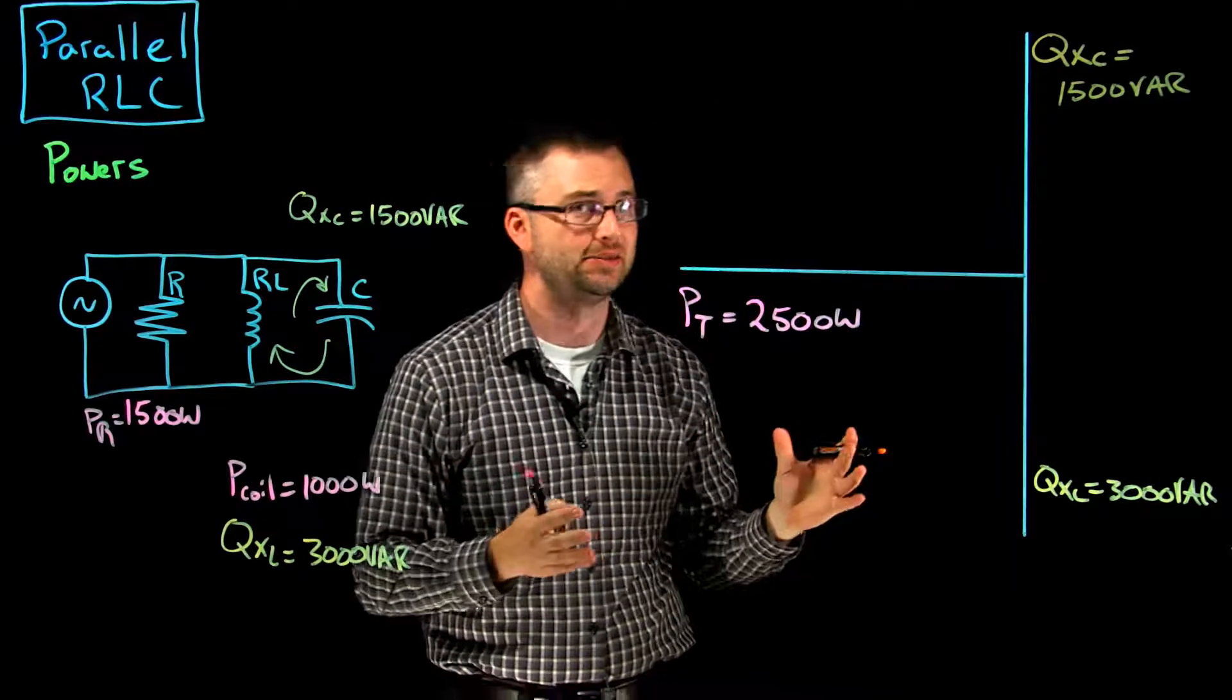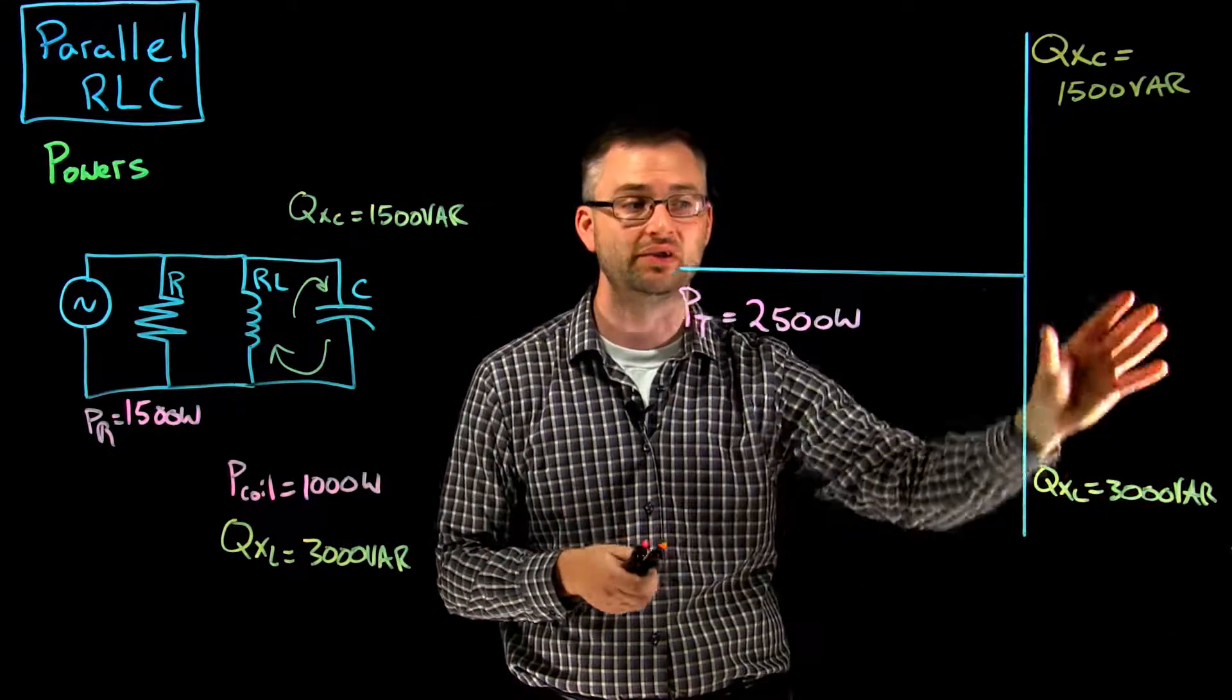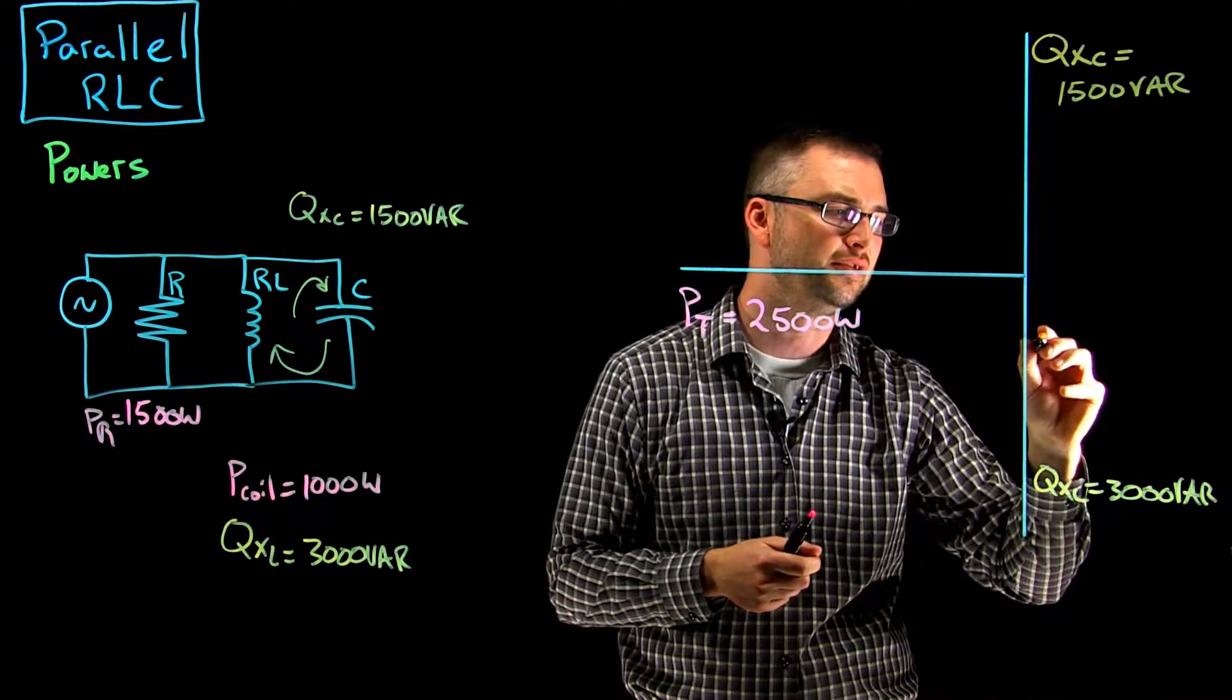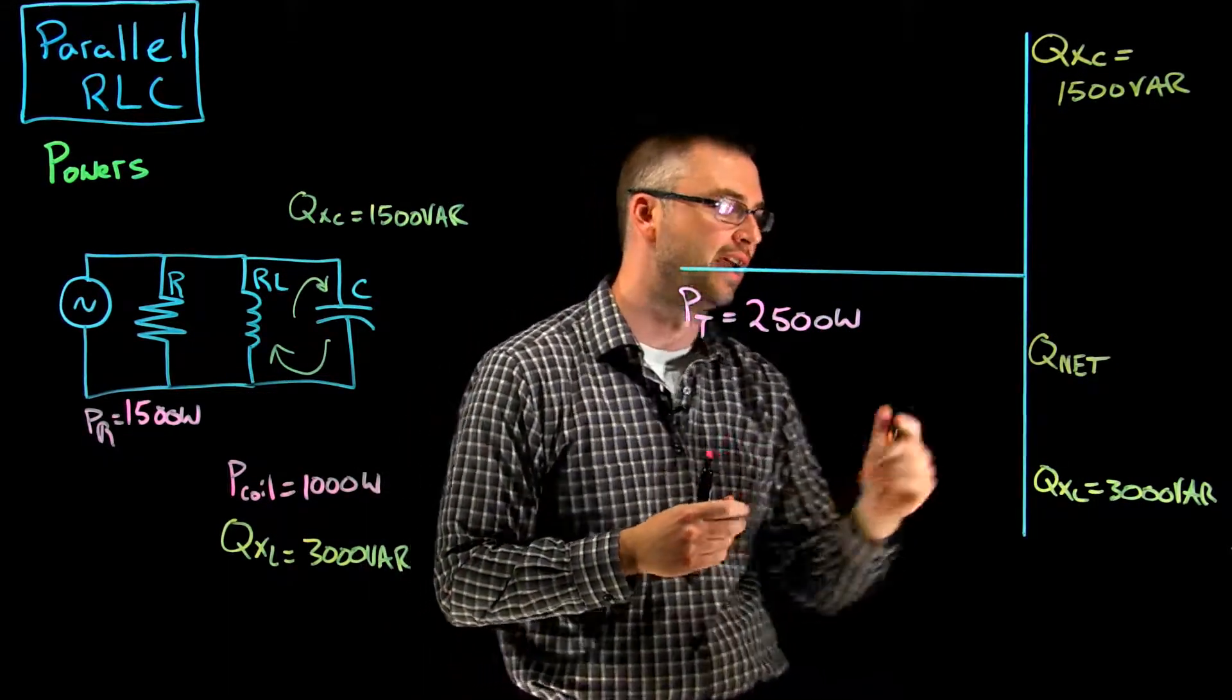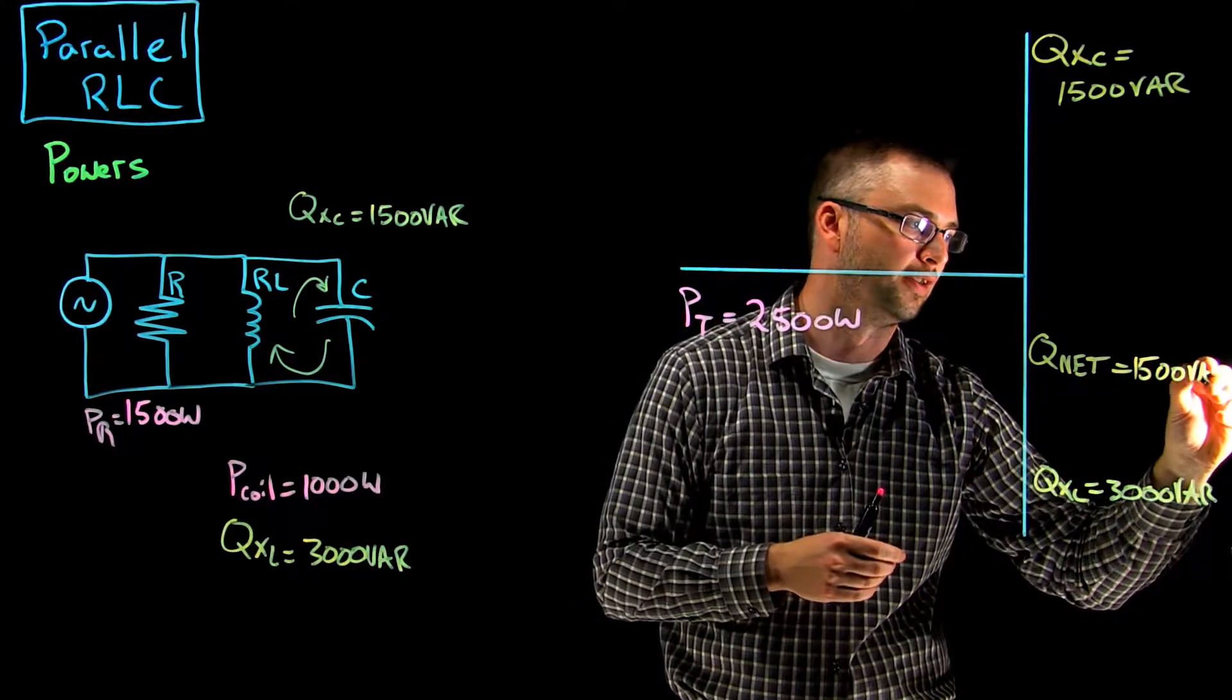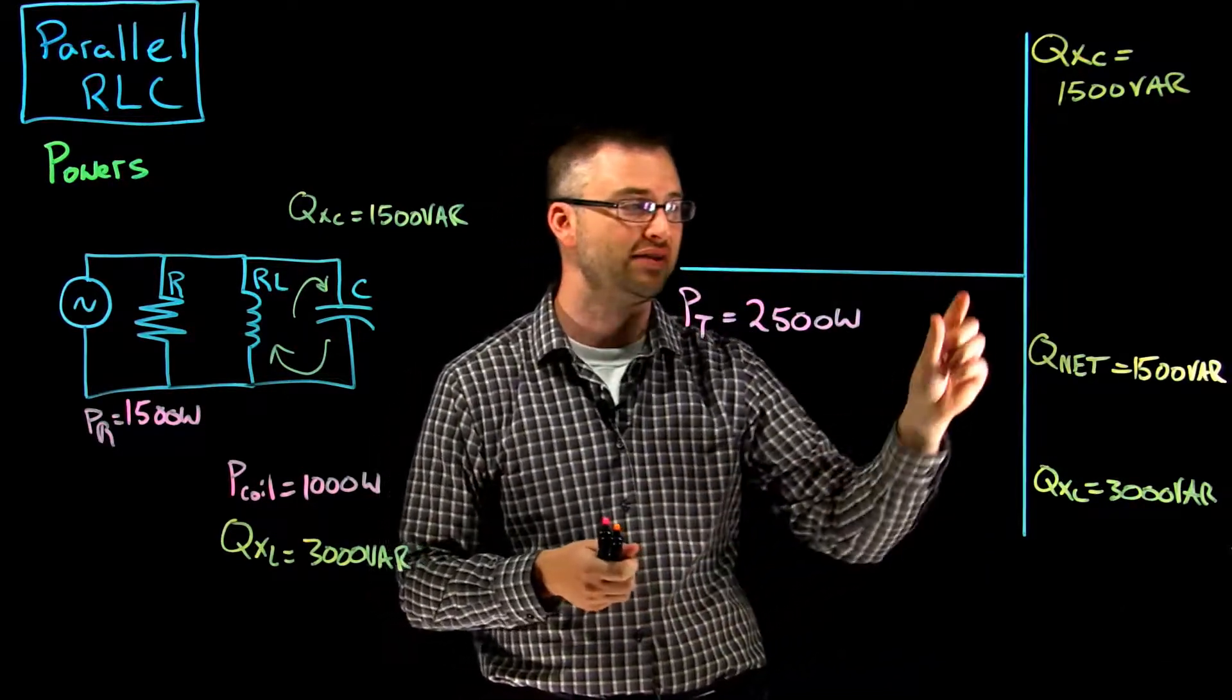Now when we add them together, they sort of cancel each other out. So 1500 VArs is going to be taken off of our 3000 VArs, and we're going to be left with a net value or a Q net. In this case it's overall more inductive, we have more lagging VArs, and it's going to be 1500 VArs in that circuit. So 3000 minus 1500, we're left with 1500 there. That is our net value.